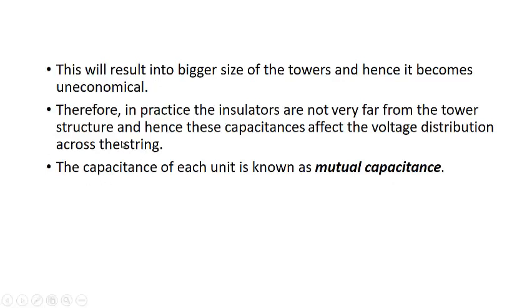The capacitance between each unit, that is between these suspension insulators, is known as mutual capacitance. The capacitance between the insulator and insulator pin and the tower structure that is connected to earth is known as earth capacitance.